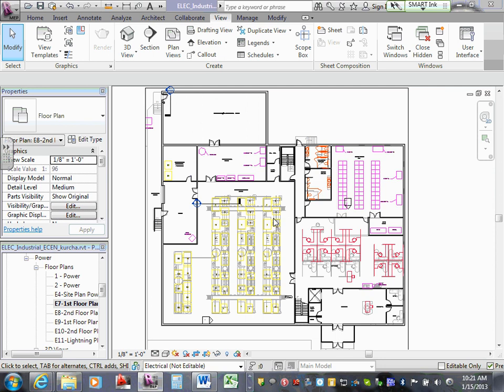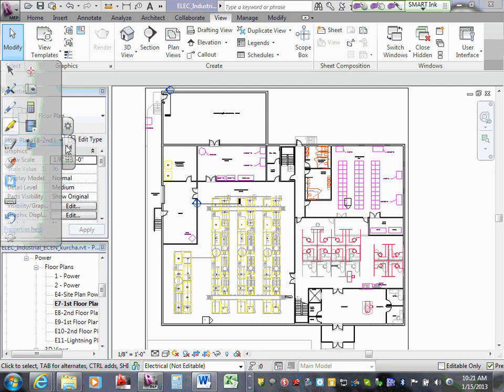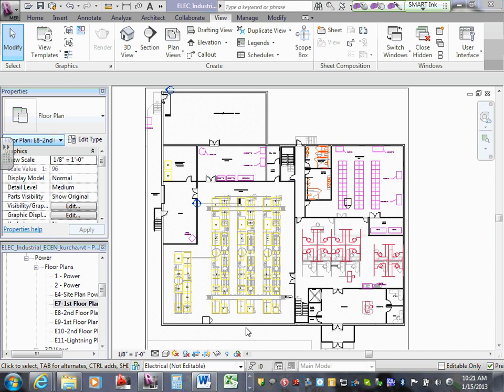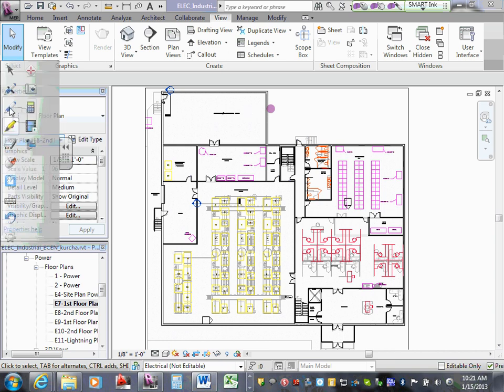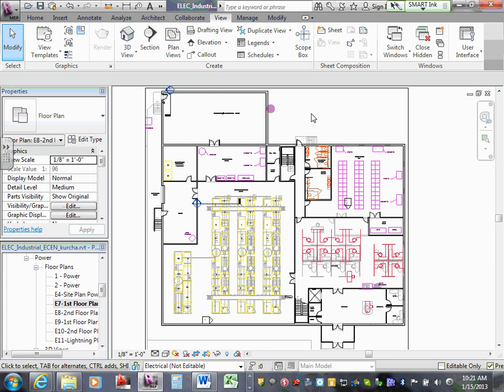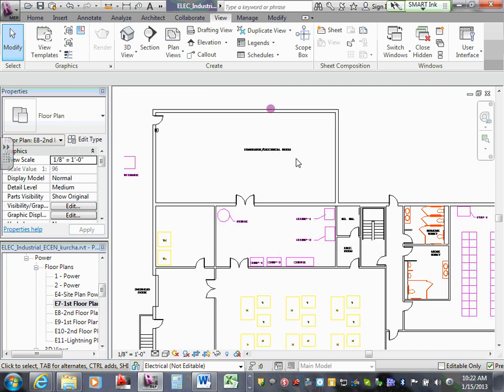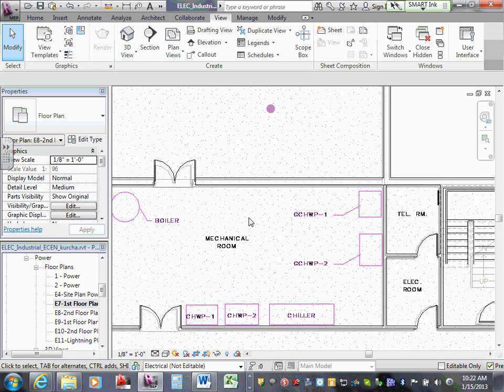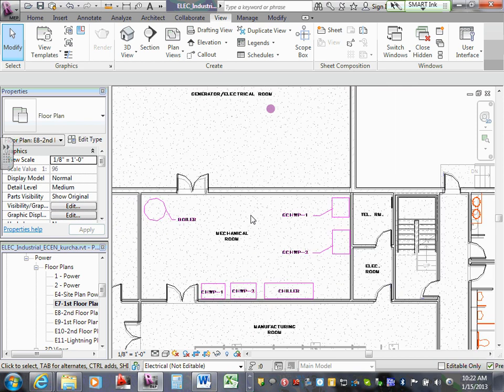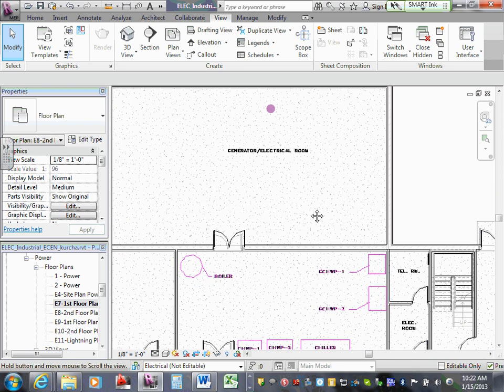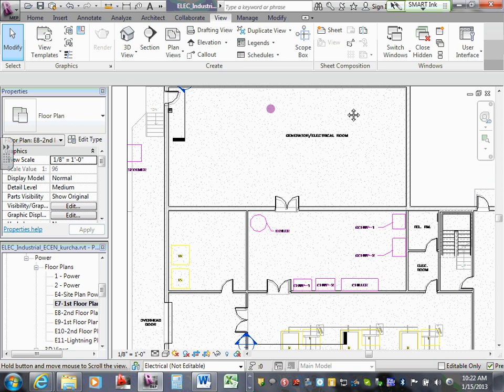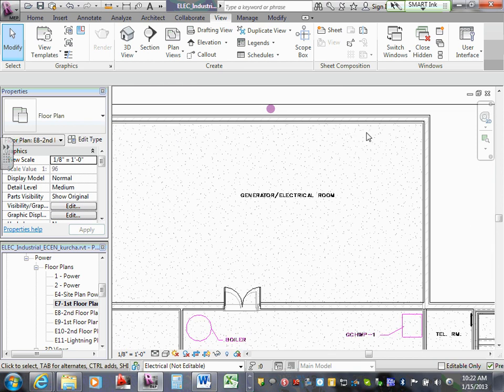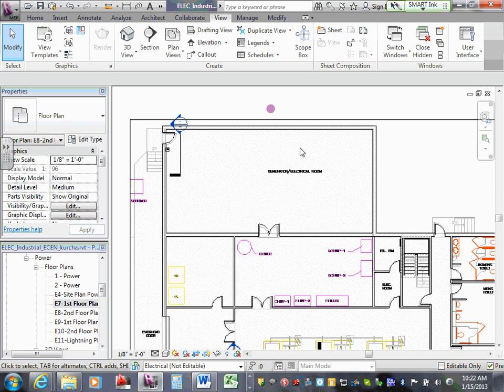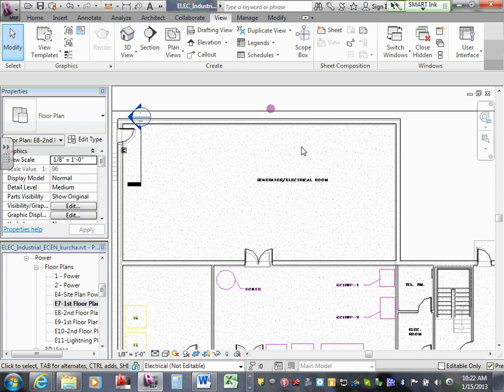start taking a look. Typically when I'm designing a fire alarm system, the first thing I like to know is where the mechanical contractor or plumbing contractor is going to put the riser for the sprinkler. And the mechanical electrical area. Yeah. I think this is mainly going to be chillers, boilers. So I imagine up here is your OS&Y valve and your sprinkler system are going to be coming in through somewhere in this back corner area. Depends on where the fire department has access to the OS&Y valve.